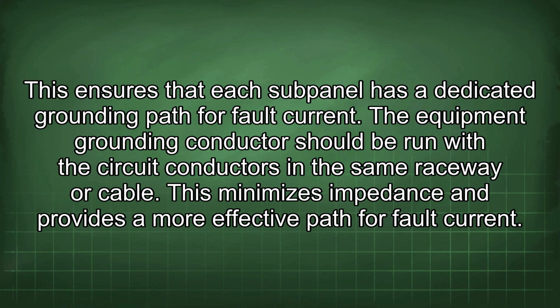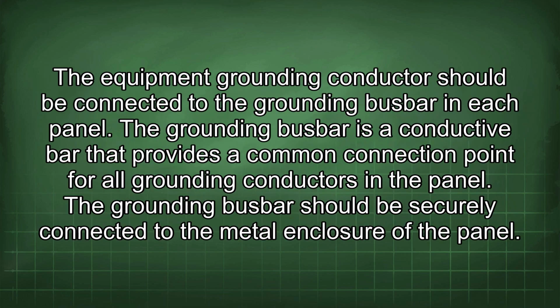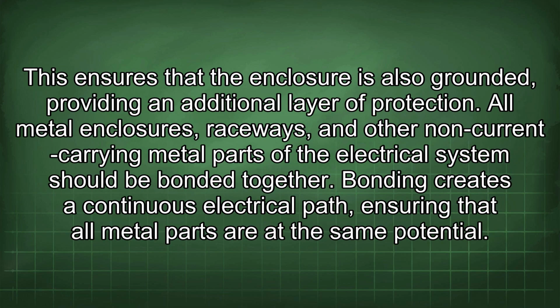The equipment grounding conductor should be run with the circuit conductors in the same raceway or cable. This minimizes impedance and provides a more effective path for fault current. The equipment grounding conductor should be connected to the grounding busbar in each panel. The grounding busbar is a conductive bar that provides a common connection point for all grounding conductors in the panel. The grounding busbar should be securely connected to the metal enclosure of the panel. This ensures that the enclosure is also grounded, providing an additional layer of protection.